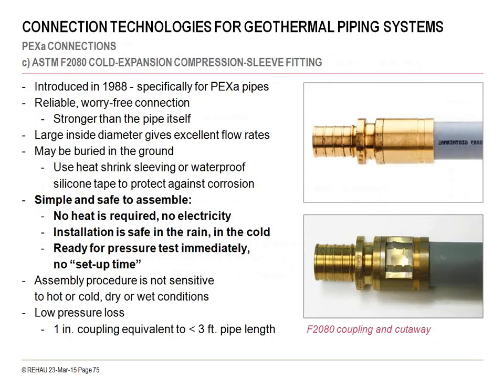So on the RAUGEO method of joining, which is this cold compression fitting system, it was introduced in 1988. It really is a bulletproof fitting system. It can be buried in the ground with the fitting in the sleeve being wrapped and protected with a waterproofing sleeve or taping material. You don't need any heat. No electricity is being used. Again, it's fine to be joining the pipes in rain if it's cold. Minimal skill level is required for this joining method.